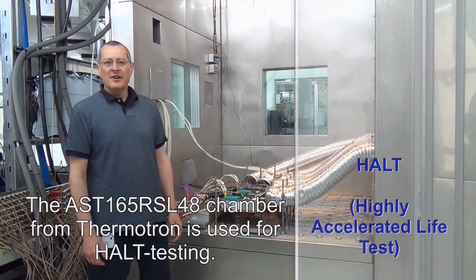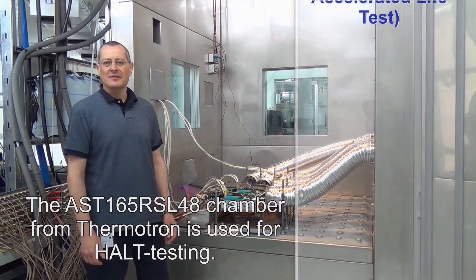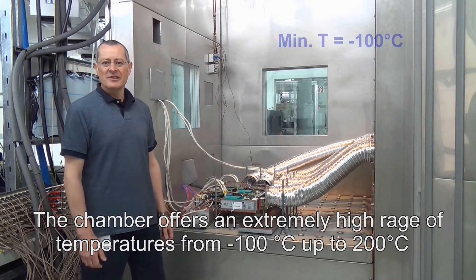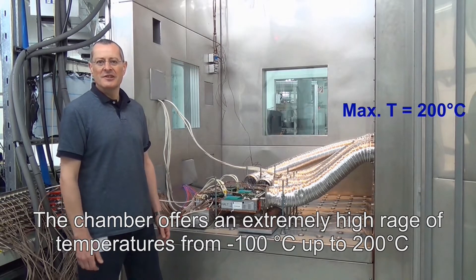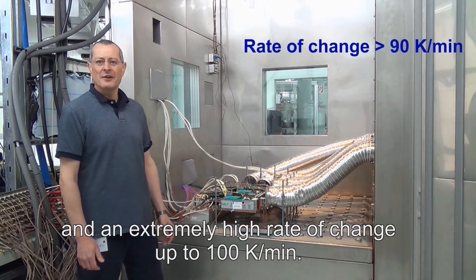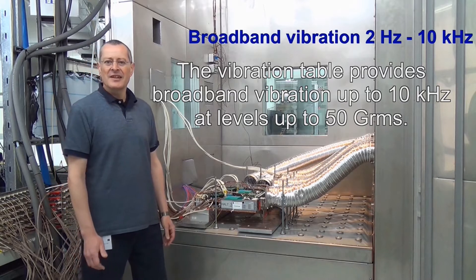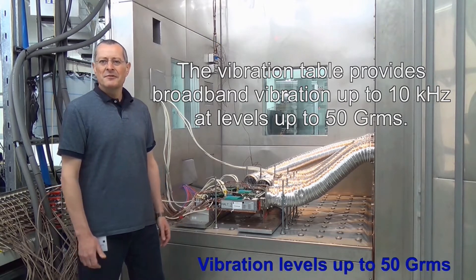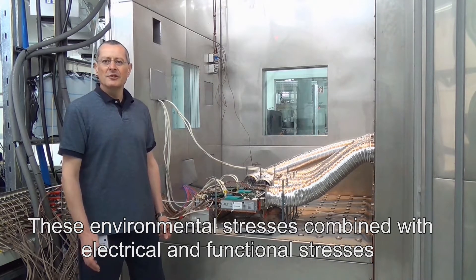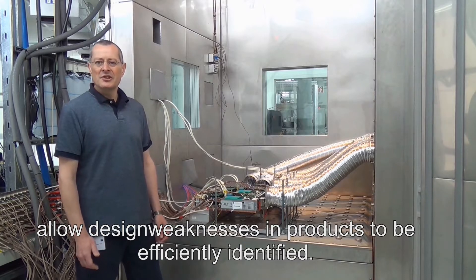The AST-165 RSL48 chamber from Thermotron is used for HALT testing. The chamber offers an extremely high range of temperatures from minus 100 degrees centigrade up to plus 200 degrees centigrade, and an extremely high rate of change up to 100 Kelvin per minute. The vibration table provides broadband vibration up to 10 kHz at levels of up to 50 G's RMS.